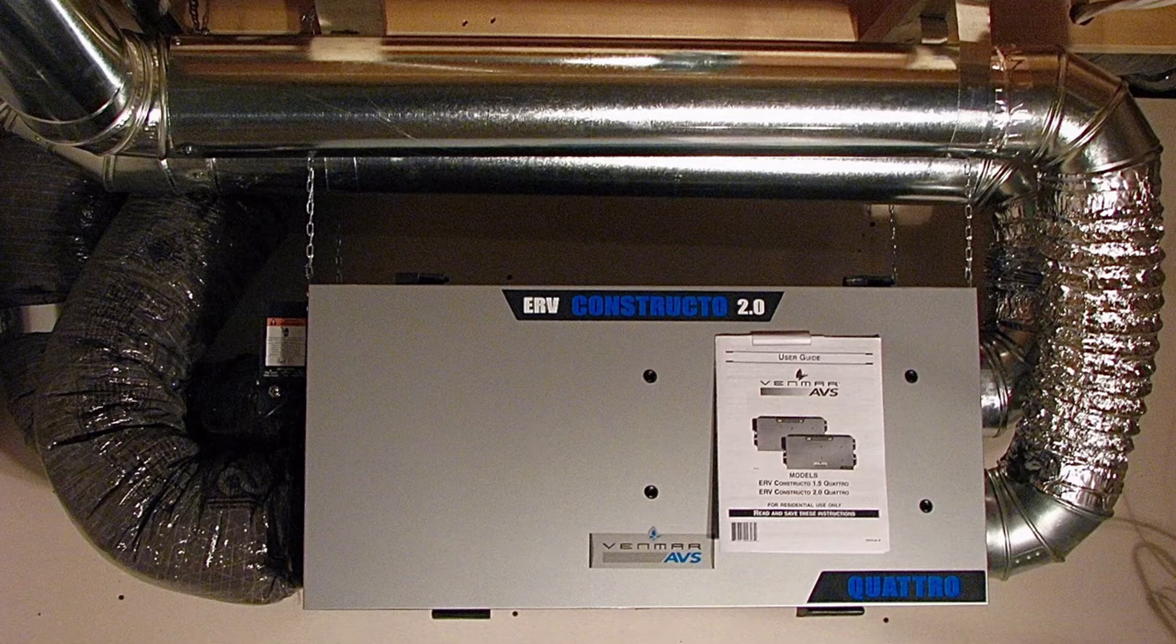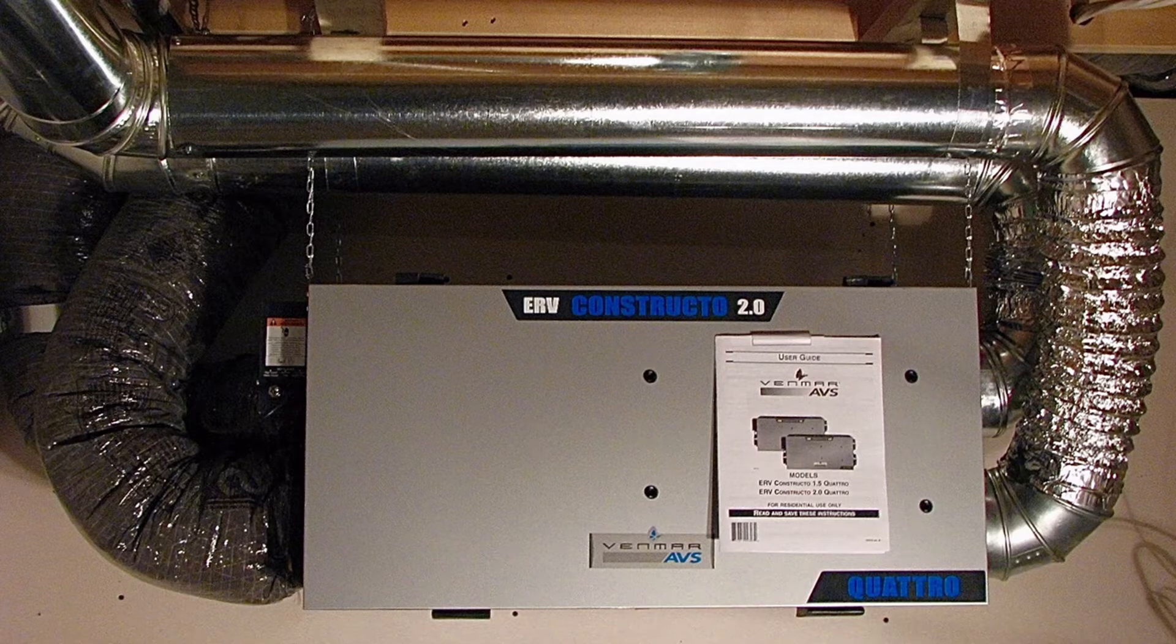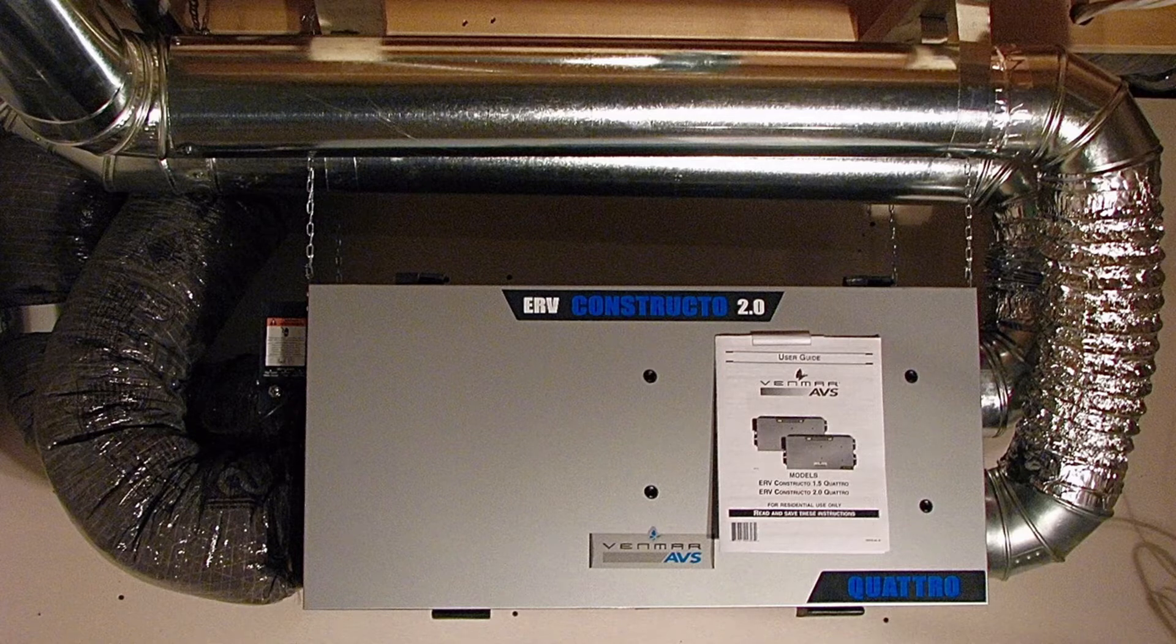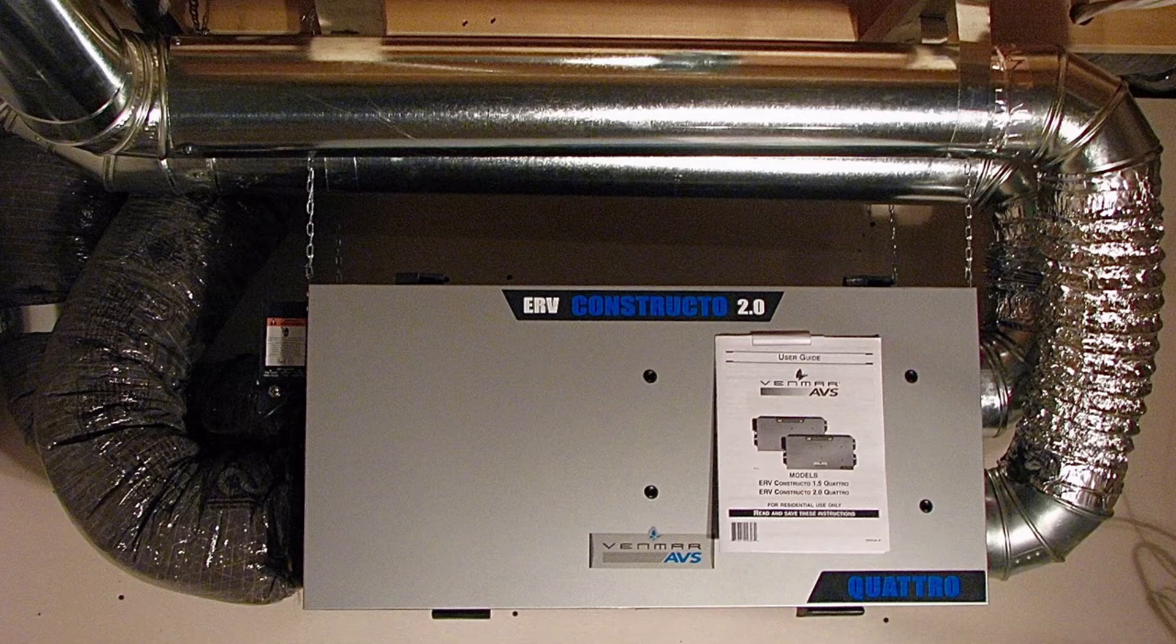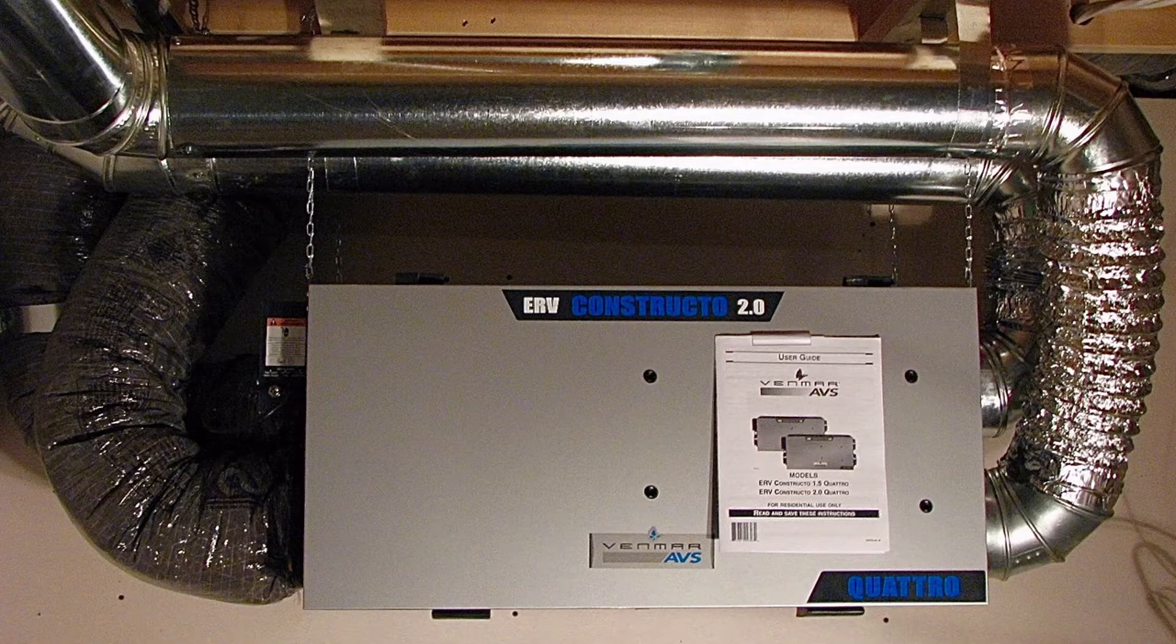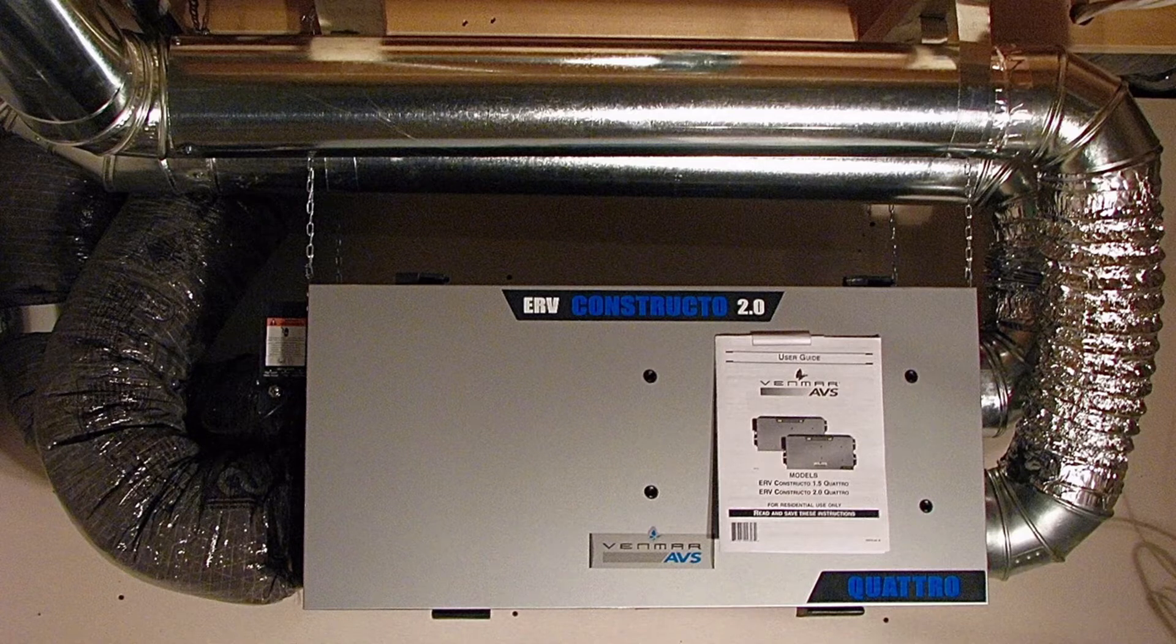Any ventilation system, as of January 2022, going into City of Vancouver dwellings requires an HRV. The City of Vancouver is unique in this way. As of January 2022, it will no longer permit other ventilation systems in any building type. This includes laneway homes, secondary suites, and single-family dwellings. HRVs will be required in every dwelling unit, and a checklist must be submitted for every dwelling unit.